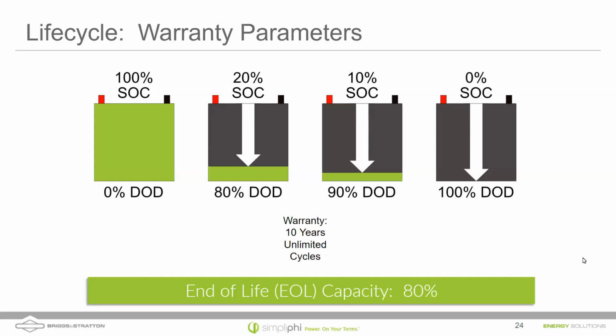And so if it's just sitting there, I'd probably go for 100% depth of discharge. But if I know that I'm going to be cycling it daily, I'd probably go for something more conservative, an 80% depth of discharge. So I get the most cycle life and the most capacity at the end of life of that battery.